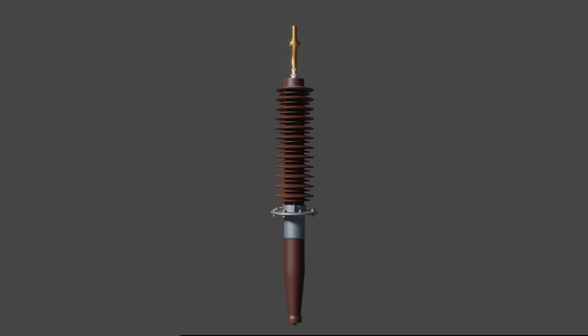This is the insulator housing. It is either made of porcelain or composite insulating material. From the flange to this portion remains in the air when fitted on the transformer. The length is decided depending upon the required minimum clearance of the live line from the earth, and these sheds serve as rain sheds as well as provide the required creepage distance.